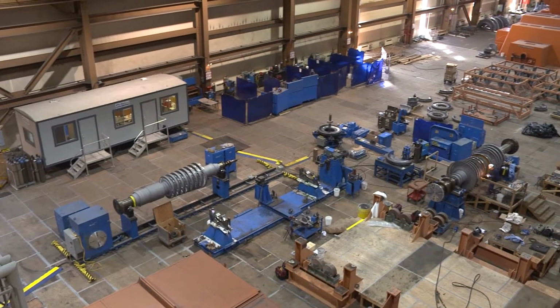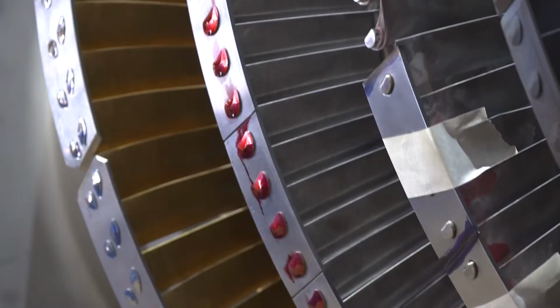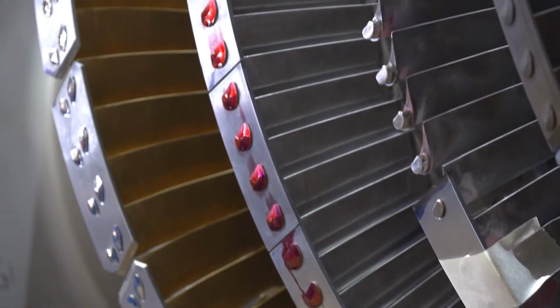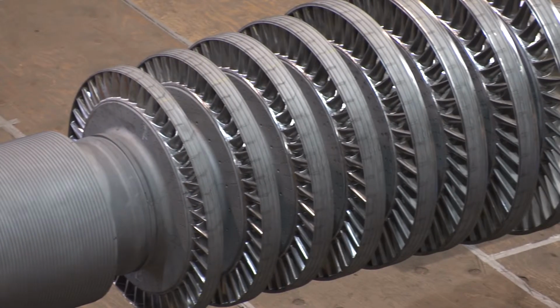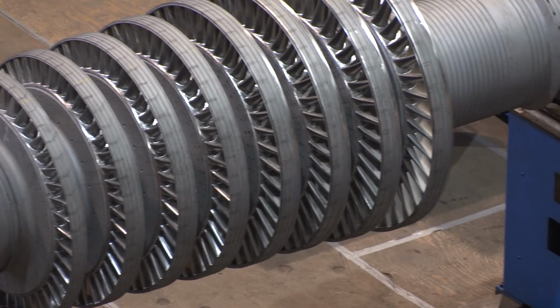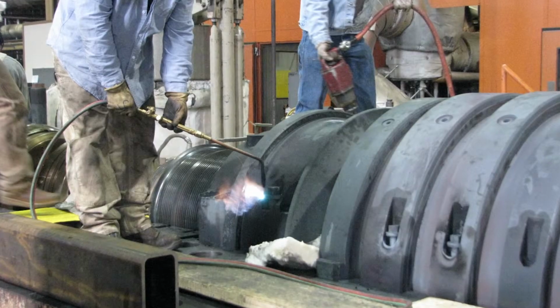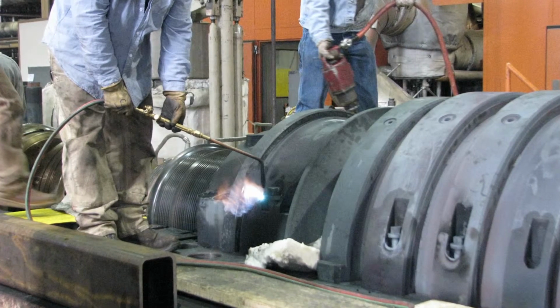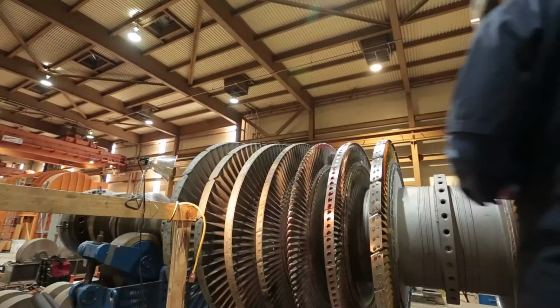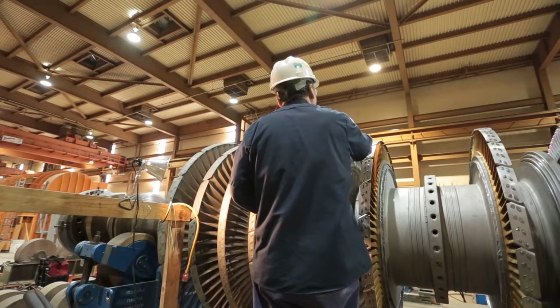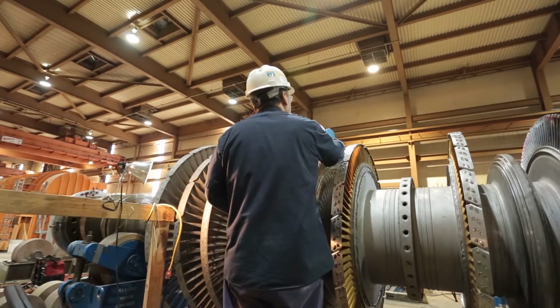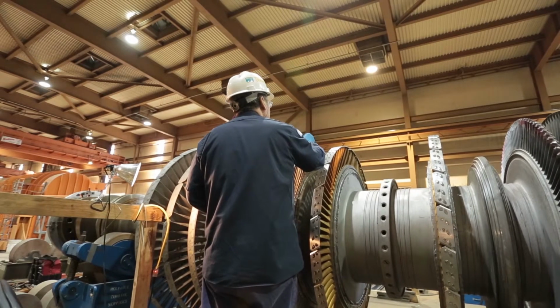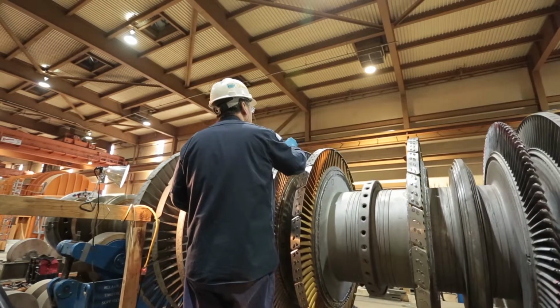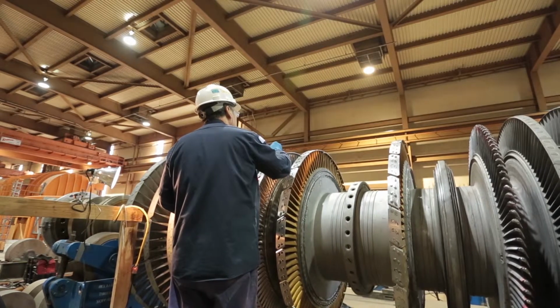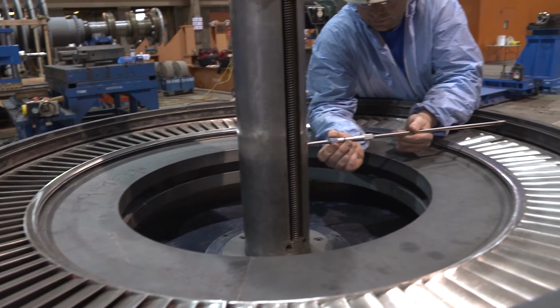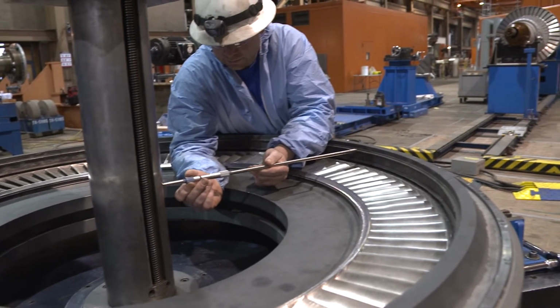A 6-week scheduled maintenance outage for Unit 1 was completed at the end of April 2014. Work on the turbine generator included: high-pressure rotor buckets were polished and all non-destructive examination on the rotor was completed. High-pressure N2 packing gland was weld repaired due to damage sustained during the removal process. Intermediate pressure rotor 8th and 9th stage buckets and covers on the turbine and generator ends were replaced along with bucket covers on the 10th stage due to solid particle erosion and foreign object damage, and all non-destructive examination on the rotor was completed. High pressure and intermediate pressure diaphragms were repaired and new spill strips installed.